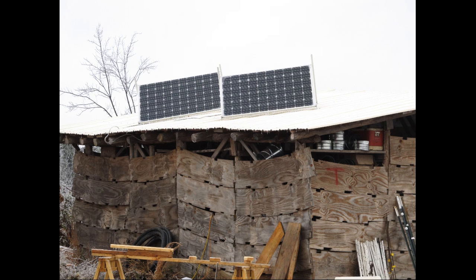There's the two photovoltaic panels that are running. They're currently running our construction tools, but they are going to run the nickel iron batteries. I got a charge controller that will work for both kinds. That's a Xantrex C40, I believe. These panels are in parallel, so they're each 30-volt panels, which will then charge a 24-volt nickel-iron system.